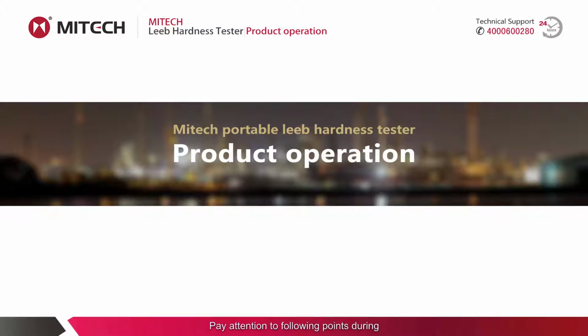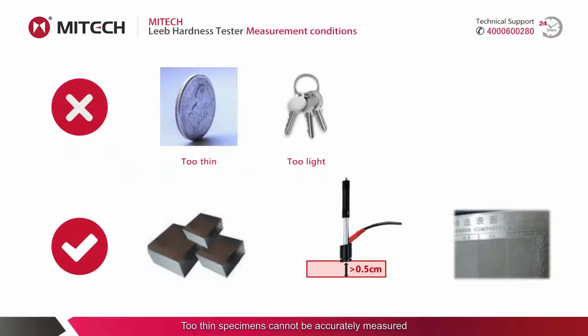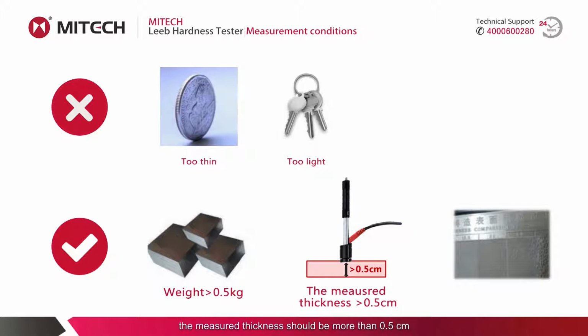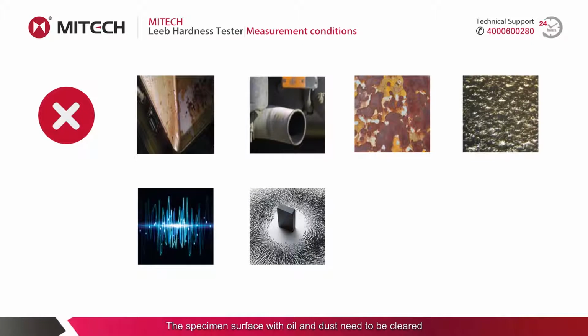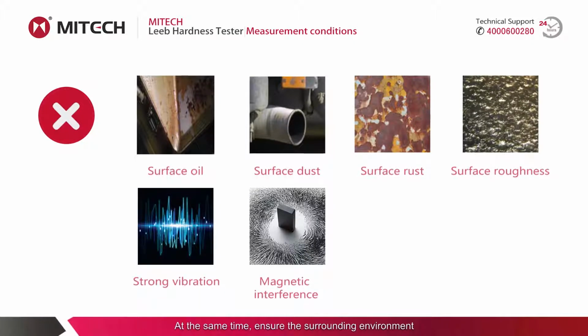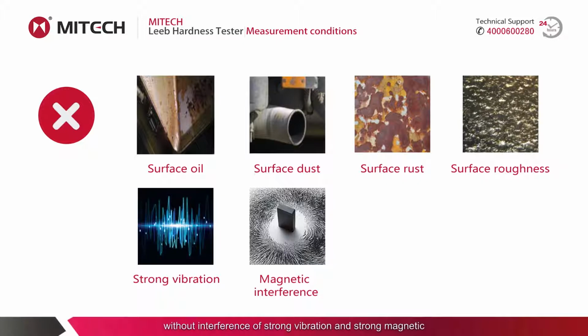Pay attention to the following points when using a portable hardness tester. Too thin specimens cannot be accurately measured. In general, the specimen weight should be more than 0.5 kg. The measured thickness should be more than 0.5 centimeters. The specimen surface roughness cannot be greater than 1.6 microns. A specimen surface with oil and dust needs to be cleaned. At the same time, ensure the surrounding environment is free from interference of strong vibration and strong magnetism, which are the basic measurement conditions for a portable hardness tester.